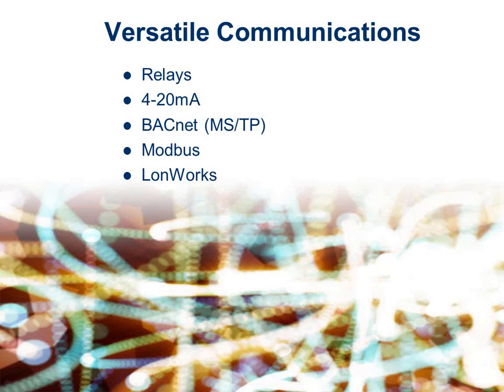I can correlate 0 parts per million to 4 milliamps, and 2,000 parts per million to 20 milliamps, then send that signal to my controller, and he knows anything in between. It's straight linear. So if you got 12 milliamps, that's halfway between 4 and 20, meaning 1,000 parts per million. Now I'll make my decisions based on that value. That's a very common way for not only gas detection sensors, but humidity sensors and all kinds of stuff we use in HVAC.